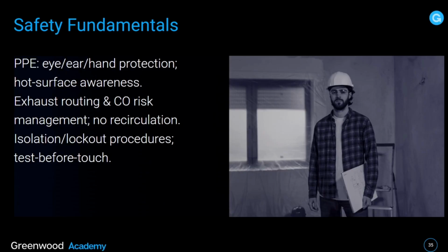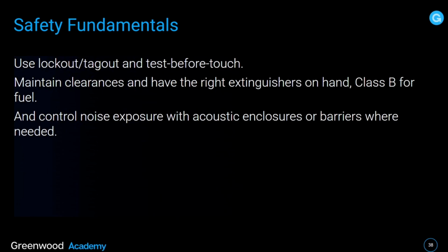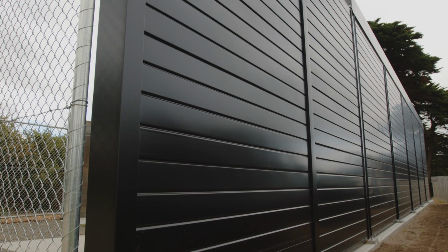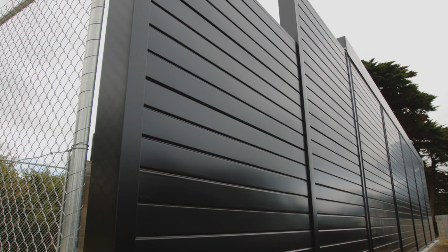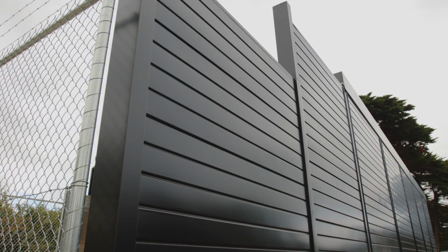So make sure there's the CO risk management, no recirculation, isolation lockout procedures, and test before touch. If the genset is indoors, it must have more than adequate ventilation at all times. Use lockout, tag out, and test before touch. Maintain clearances and have the right extinguishers on hand. Class B for fuel. And control noise exposure with acoustic enclosures or barriers where needed.